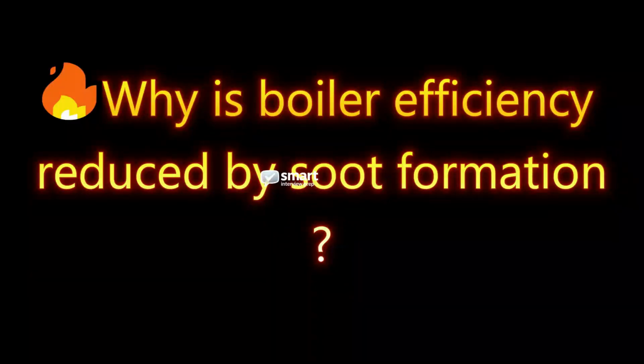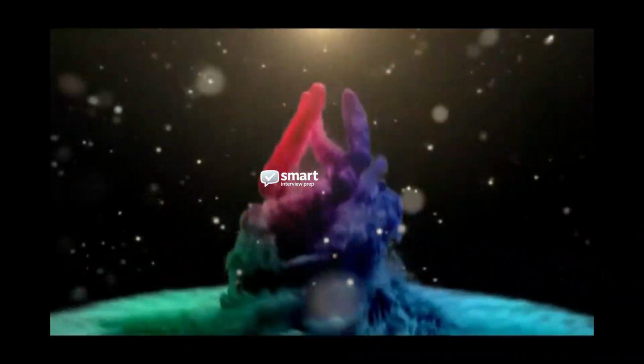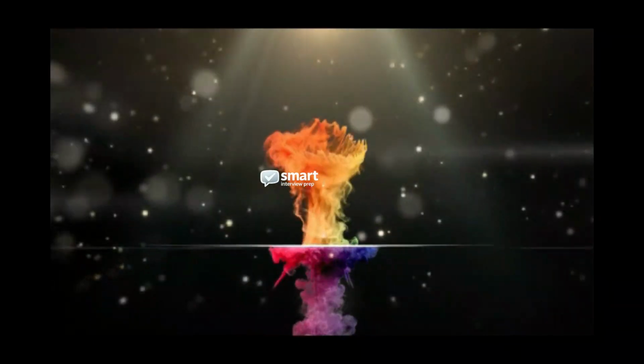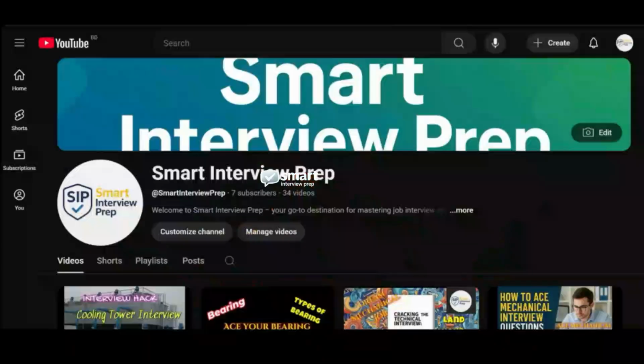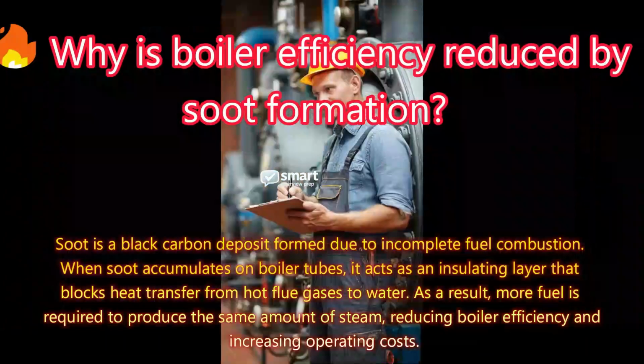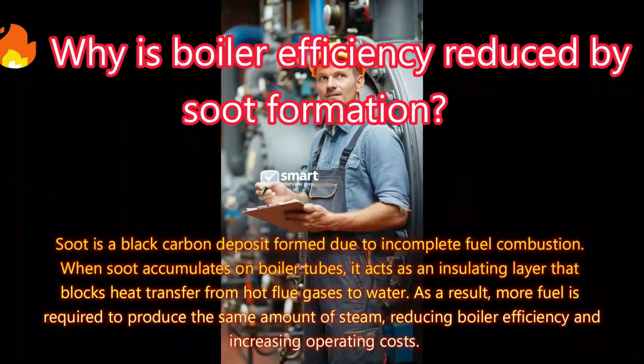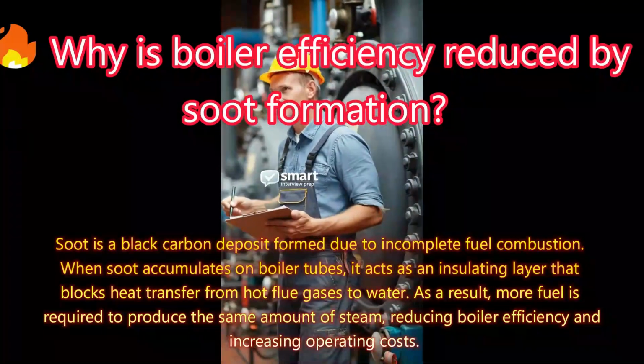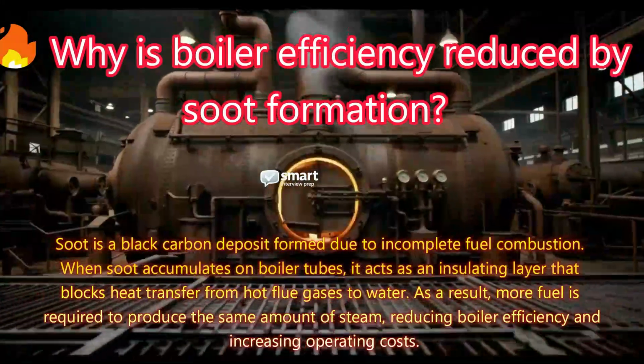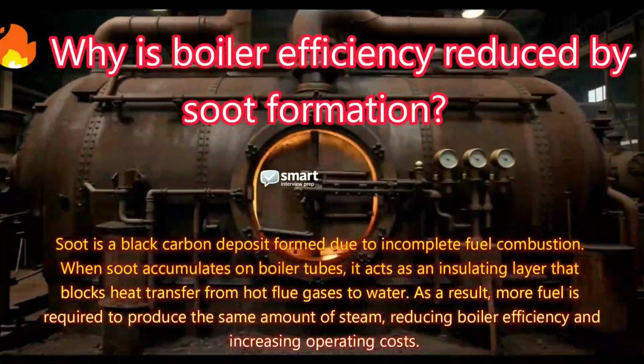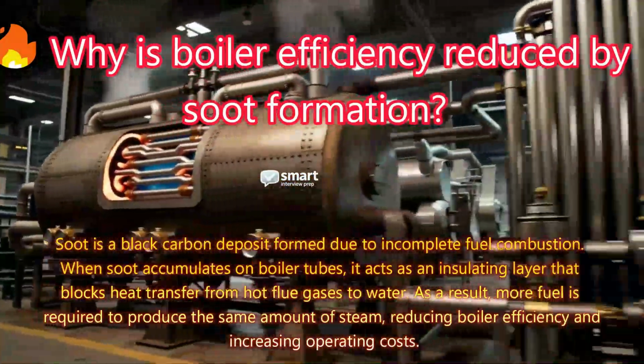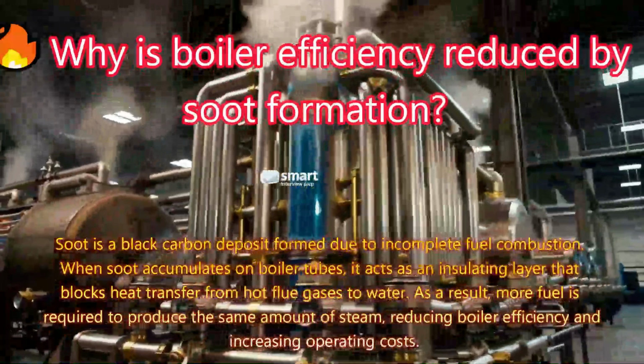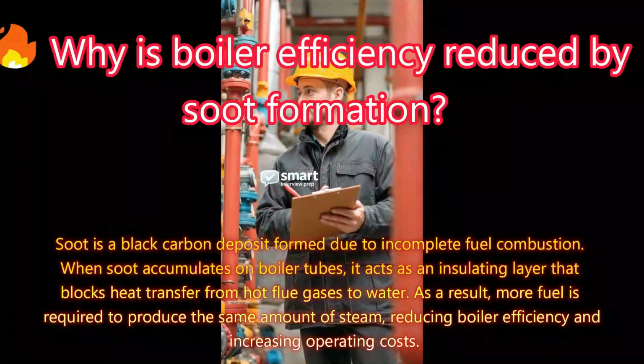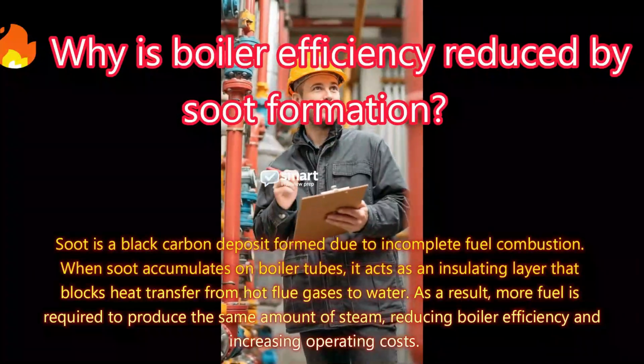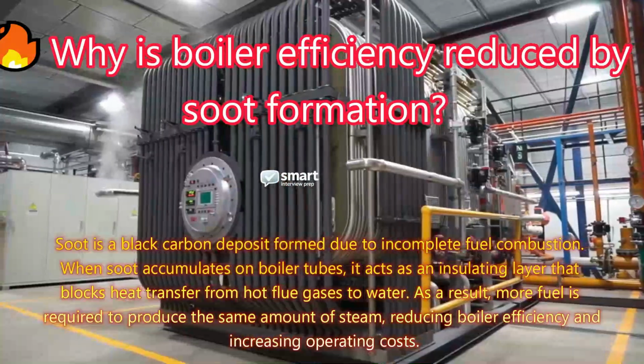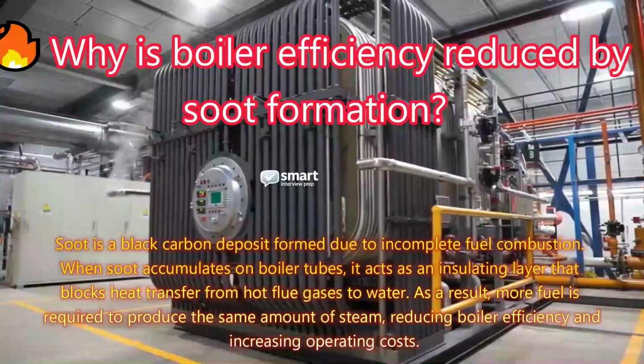Why is boiler efficiency reduced by soot formation? Answer. Soot is a black carbon deposit formed due to incomplete fuel combustion. When soot accumulates on boiler tubes, it acts as an insulating layer that blocks heat transfer from hot flue gases to water. As a result, more fuel is required to produce the same amount of steam, reducing boiler efficiency and increasing operating costs.